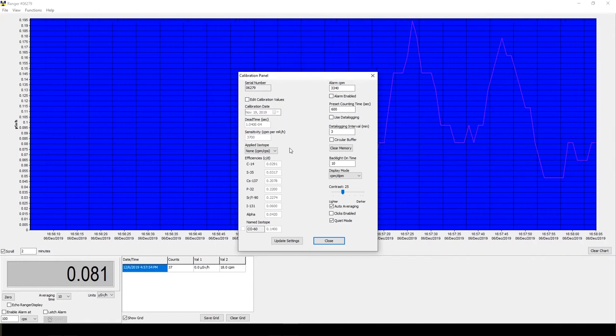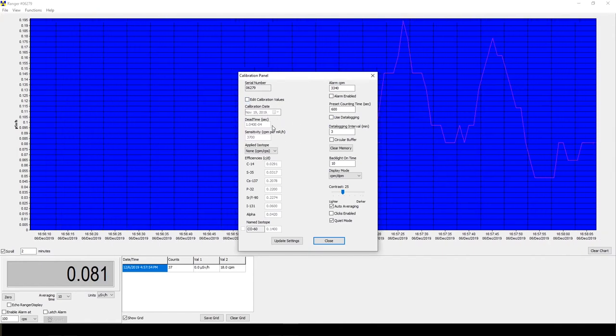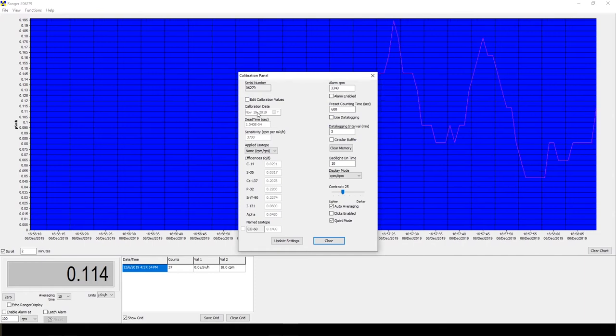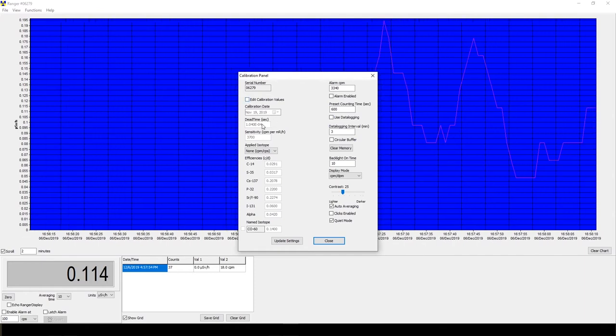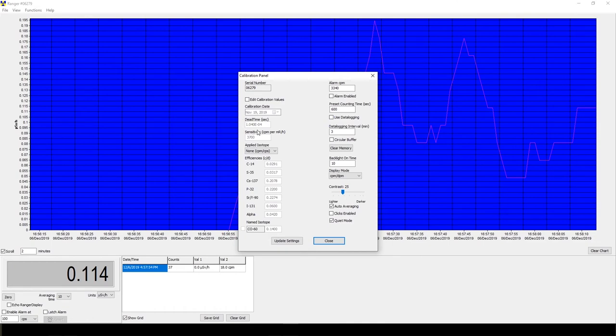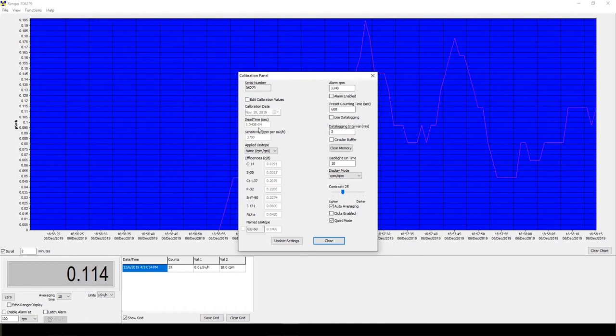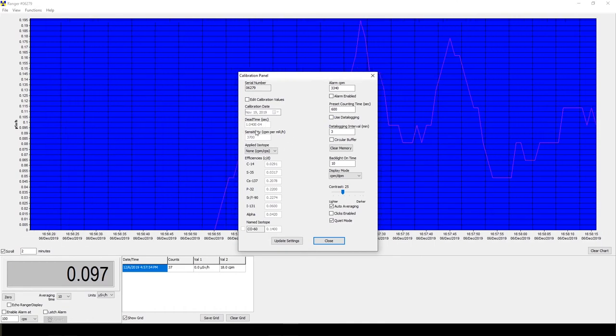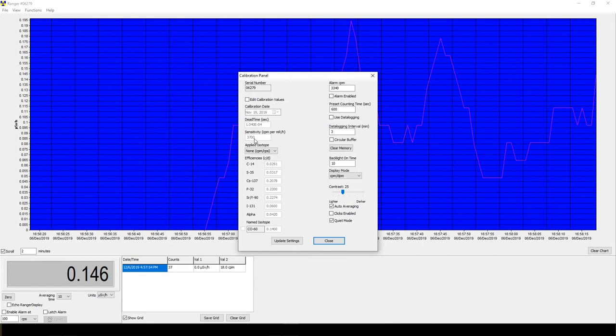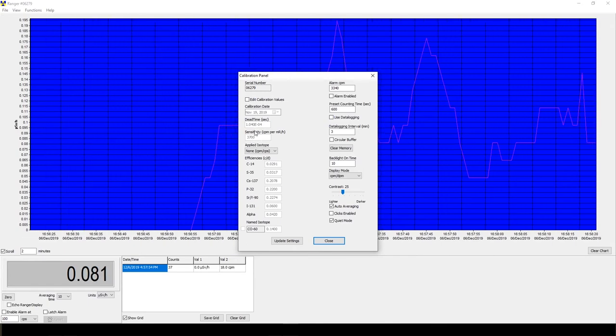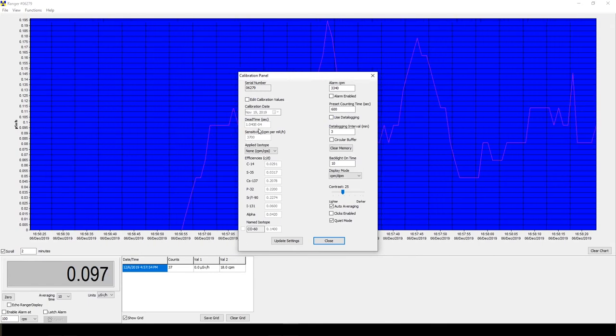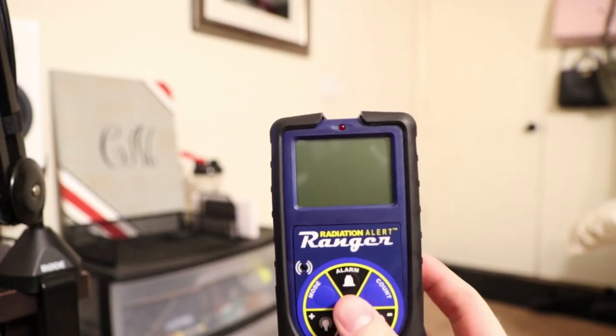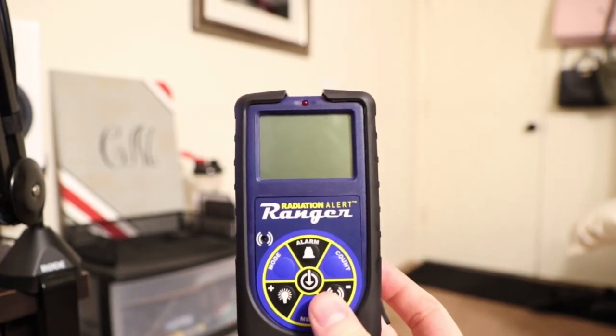You don't want to touch that when it gets calibrated from SE International. Just don't mess with anything. But you can see where the dead time right here was changed and our gamma sensitivity was changed right here, so showing 3700 and 1.040e-04. Pretty neat.